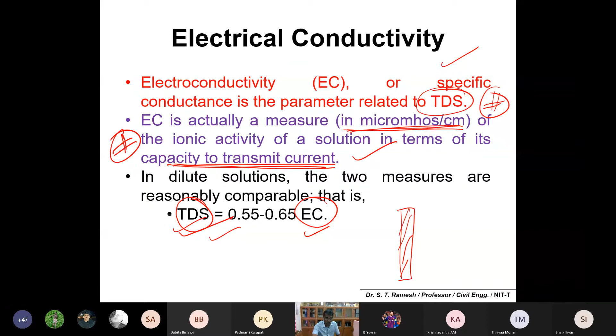So please make a note, TDS is equal to 0.55 to 0.65 times electrical conductivity. Okay, electrical conductivity is easy to measure because it is the ability to transmit current. So you can have sensors that measure the conductivity of the sample instantly. Because TDS, if you go with a gravimetric measurement, as we discussed in solids, takes time. You have to take out the filtered sample and go for a gravimetric method. You evaporate all the water or moisture, and the initial and final weight you can express in terms of total dissolved solids. But conductivity you can measure very instantly. So based on the conductivity, you can calculate TDS of the sample using this formula, 0.55 to 0.65 times electrical conductivity.